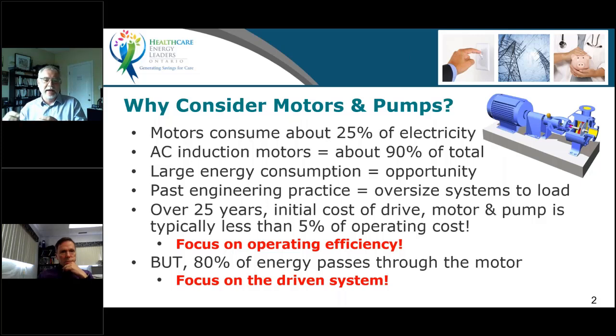But when you look at maintenance of that pump too, that's another piece I would add in here, and I'm going to speak to that in a few minutes. So operating a pump inefficiently will also result in probably reduced reliability as well. And so there's a dual win on this one. Now, the other thing, when it comes to the motor and pump, 80% of the energy passes through the motor or more. So is the motor the problem, or is it what the motor is connected to, what we call the driven system? Is the pump the problem, or is it the driven system?